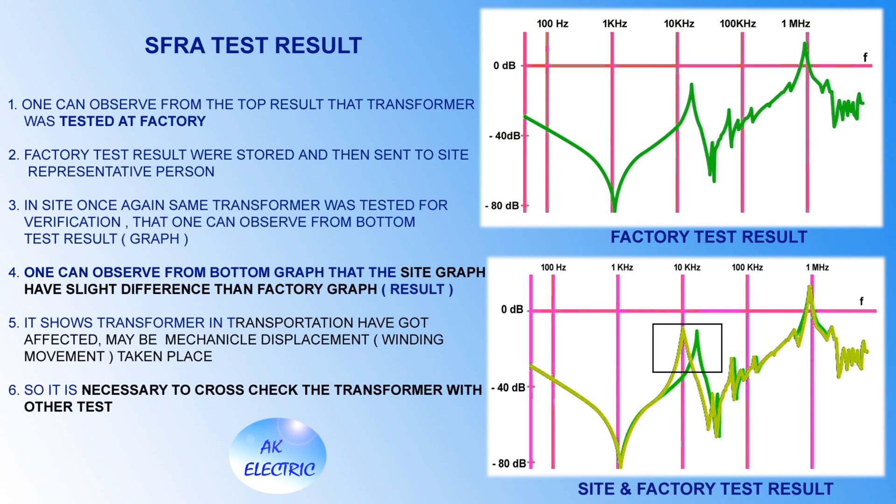For SFRA test results: the transformer is first tested at the factory, and factory test results are stored and sent to the site representative. At site, the same transformer is tested again for verification. One can observe that the site graph shows a slight difference from the factory graph at around 10 kHz, indicating the transformer was affected during transportation — possibly mechanical displacement or winding movement. It is therefore necessary to cross-check the transformer with other tests.